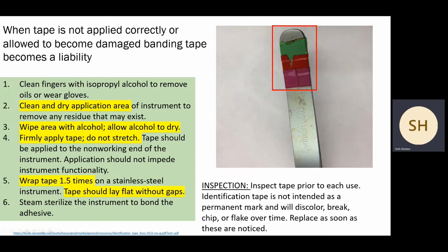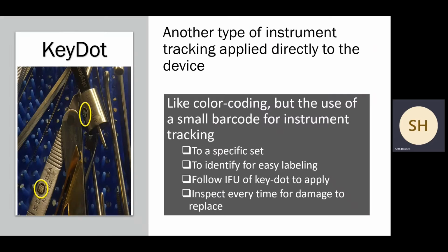Well, what do we have here? We have tape not fully wrapped around. This didn't make the 1.5 times. It has a big giant gap. There's residues sticking out, and this overlap is not good on all three of these. When you're doing inspection, inspect tape prior to each use. Identification tape is not intended as a permanent mark and will discolor, break, chip, and flake over time. And you have to replace it as soon as that is seen. And if you're not doing that, you're going to have a problem at your next survey.